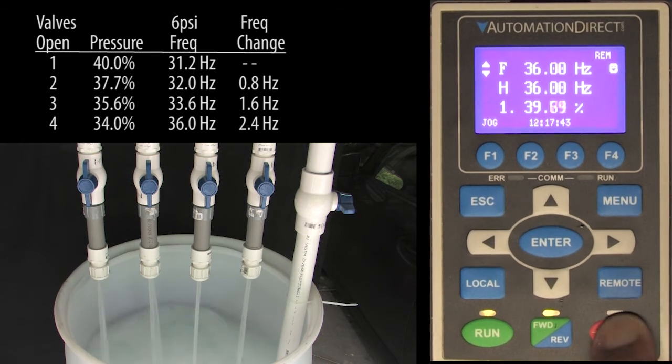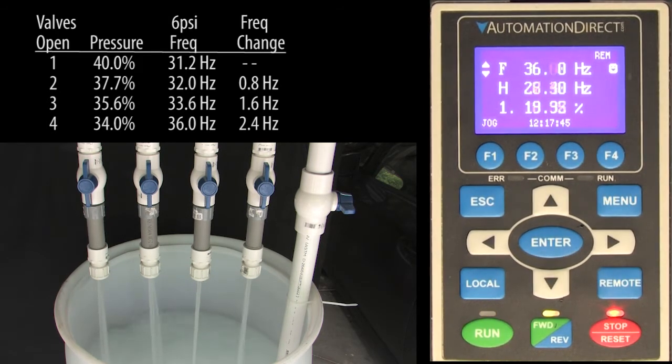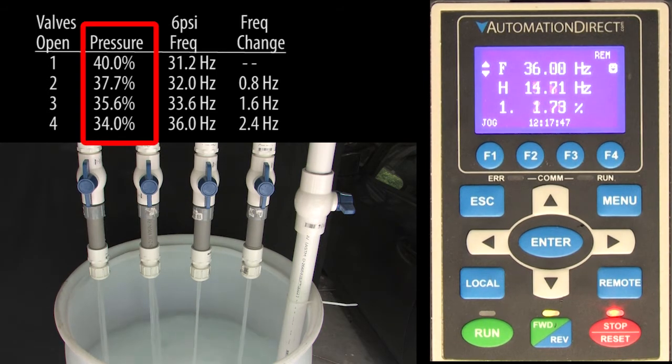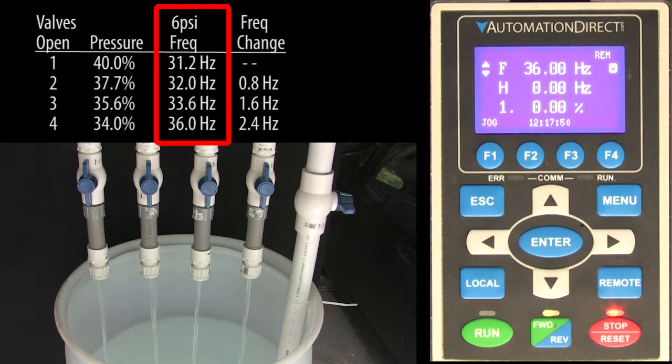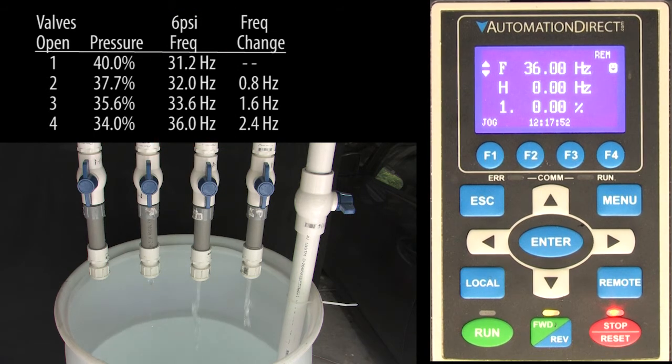So we just manually did what we want the drive to do automatically, right? Every time the pressure dropped, we manually added more drive frequency to compensate. Well, that's exactly what we want the drive's PID function to do for us.